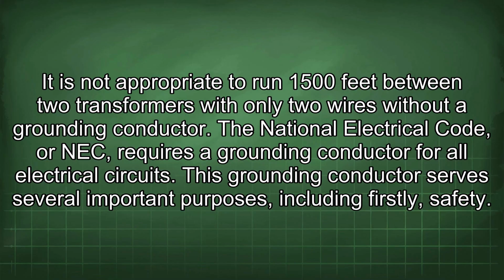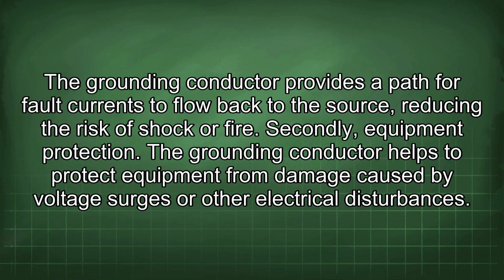It is not appropriate to run 1500 feet between two transformers with only two wires without a grounding conductor. The National Electrical Code, or NEC, requires a grounding conductor for all electrical circuits. This grounding conductor serves several important purposes, including firstly, safety. The grounding conductor provides a path for fault currents to flow back to the source, reducing the risk of shock or fire.